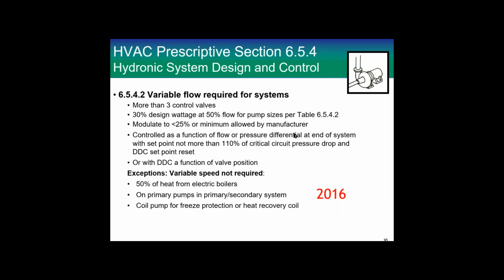All right. Now, hydraulic. We're going to move from the air side to the water side, and the variable flow required for this system. So now, to have to put a variable flow in there, you have to have more than 3 control valves. So you have to have something that's going to be able to vary the flow. 30% of the design wattage at 50% of the flow for pump sizes per this table. So what we've always come up with is that a variable speed drive will lower the wattage to 30% at 50% of the flow. You can use something else on pumps.